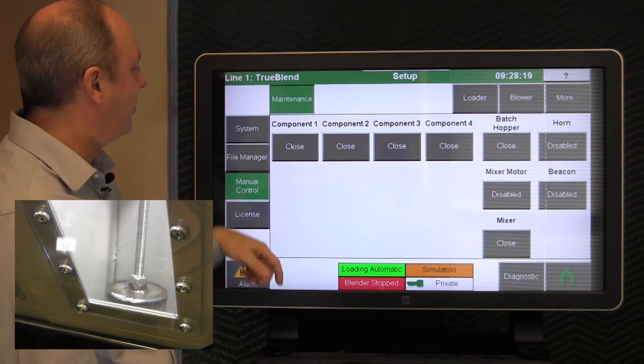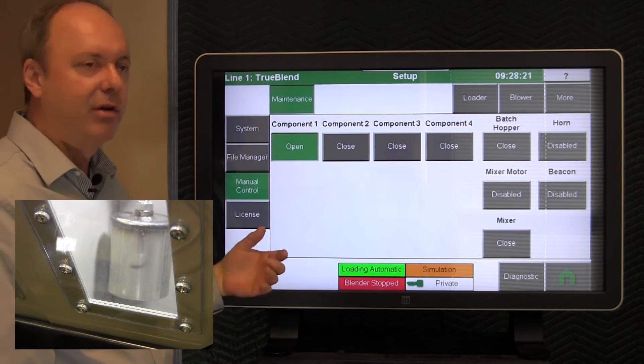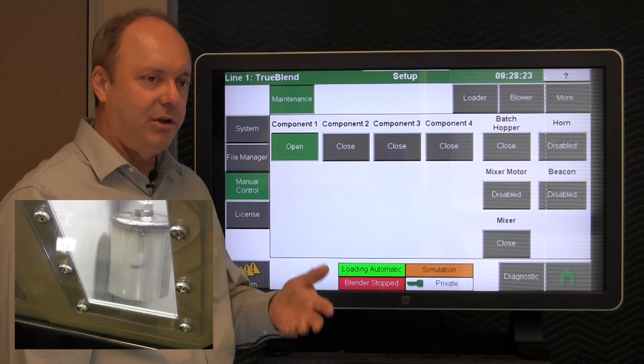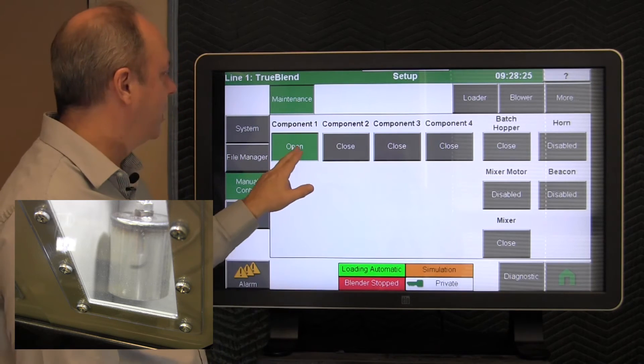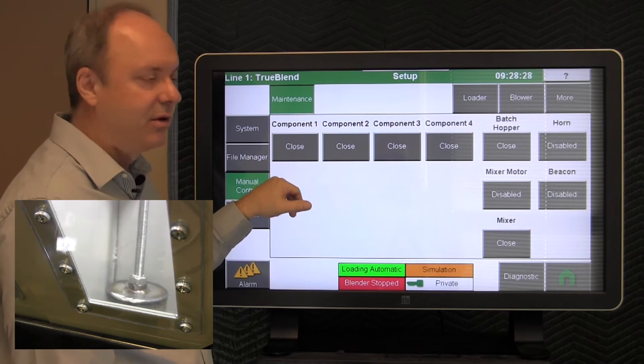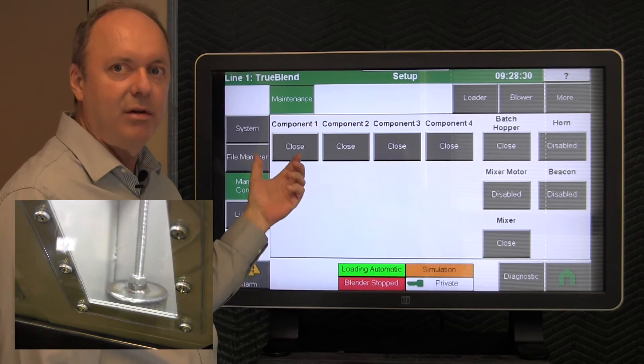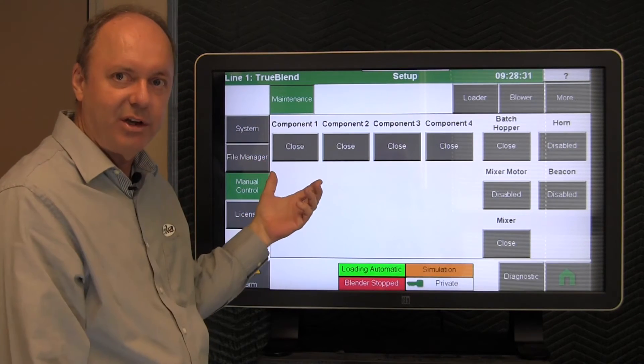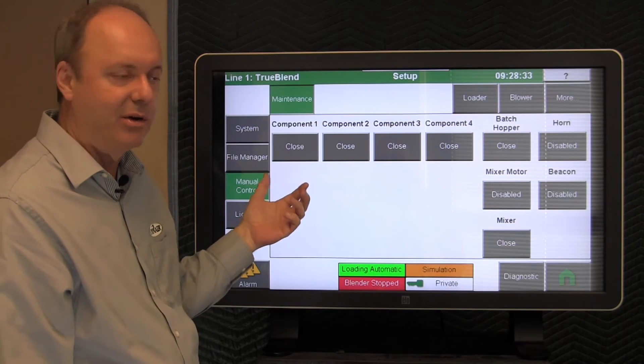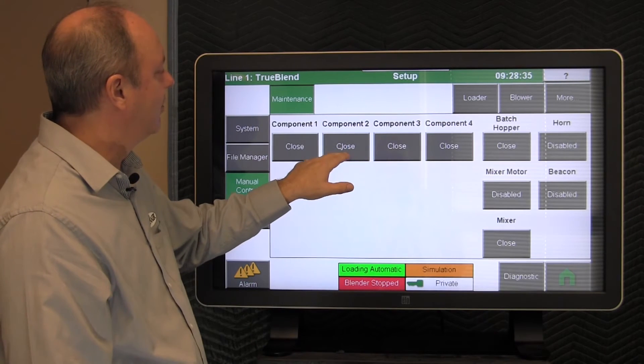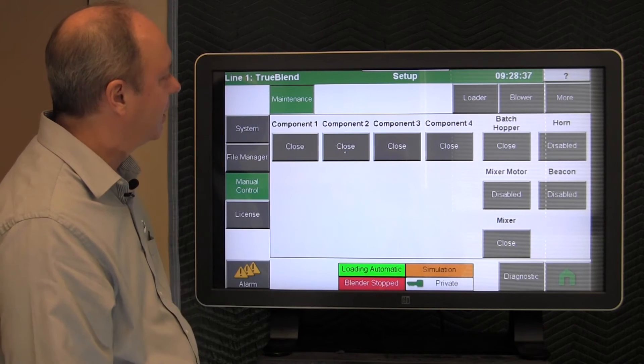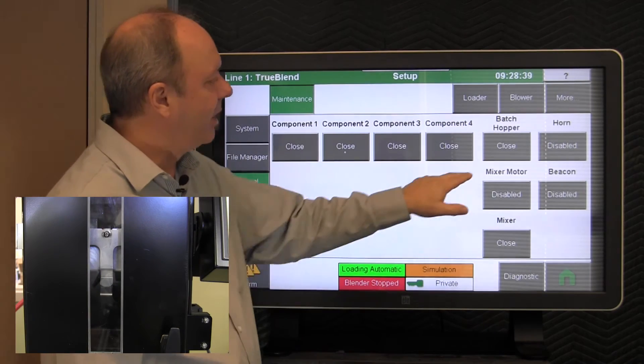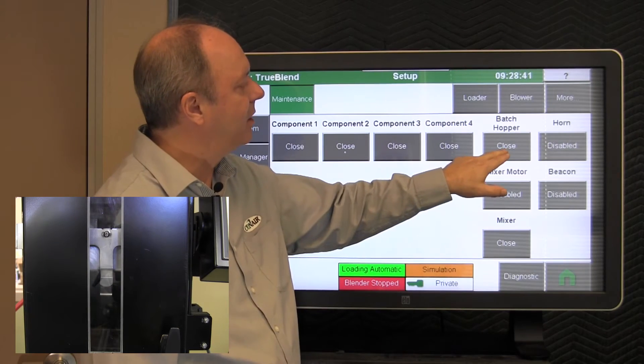You just tap them and it opens the valve. You would go and view it to be sure that it's actually opening properly and opening and closing. And you can also hear it open and close because it is a pneumatic valve. They're noisy enough where you can typically hear what they're doing. And you would test each one of them in the system just to be sure they work properly.